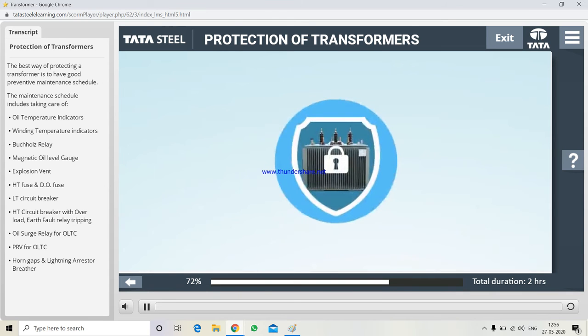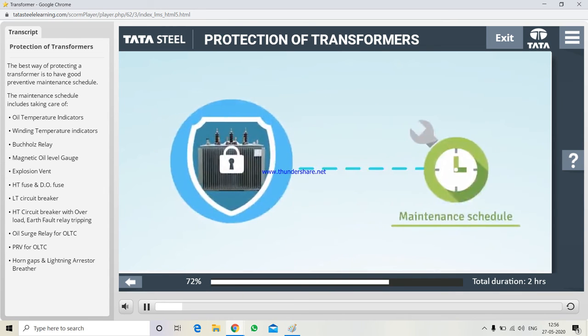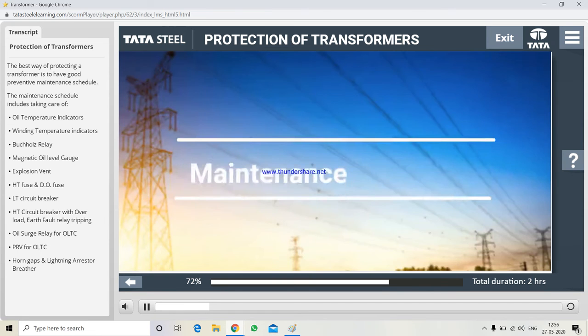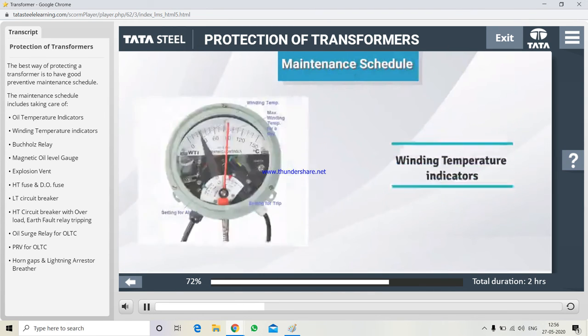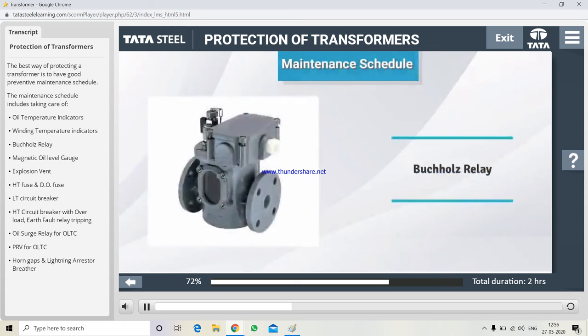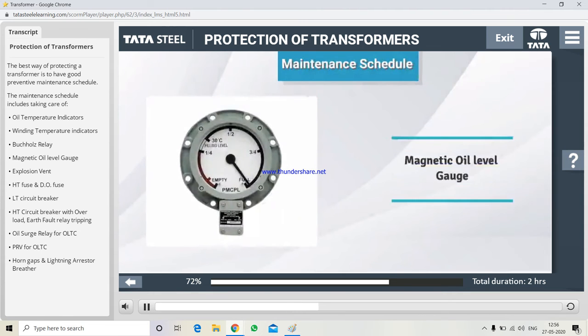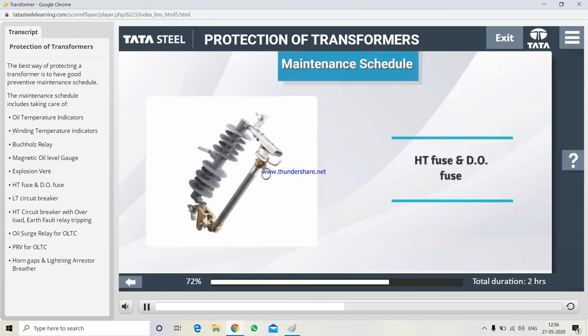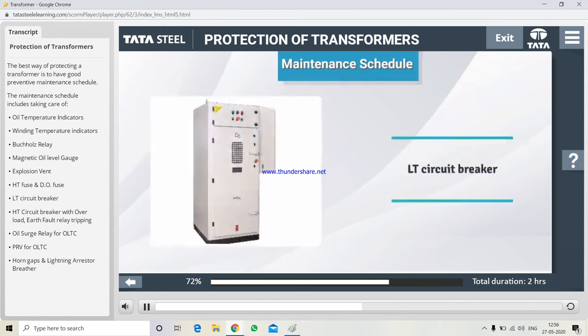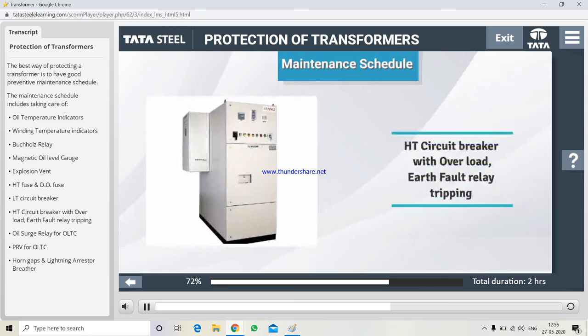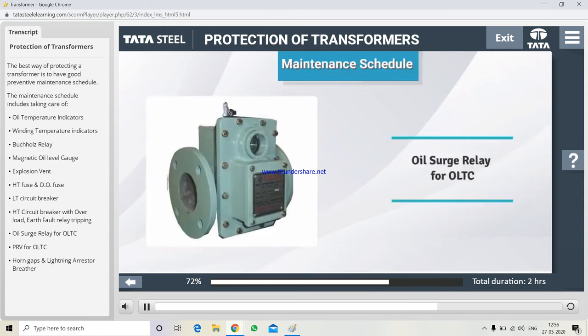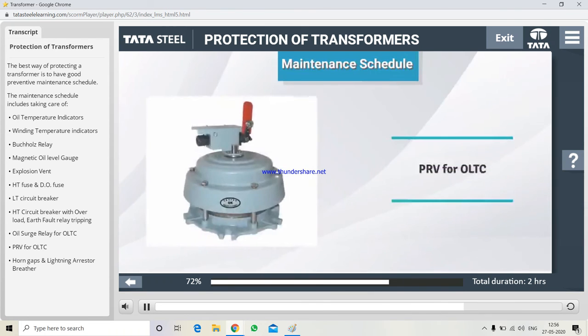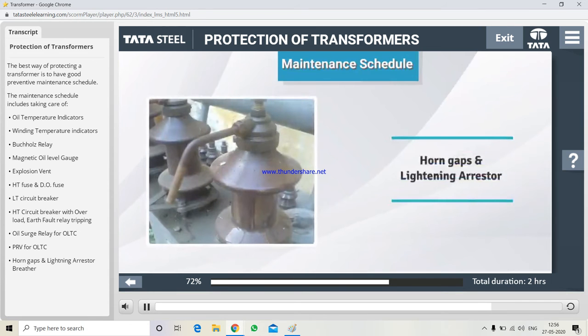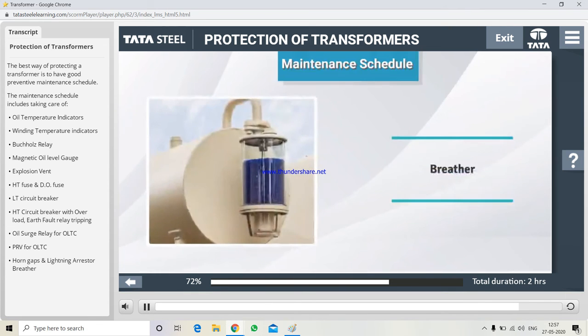The best way of protecting a transformer is to have a good preventive maintenance schedule. The maintenance schedule includes taking care of oil temperature indicators, winding temperature indicators, Buchholz relay, magnetic oil level gauge, explosion vent, HT fuse and DO fuse, LT circuit breaker, HT circuit breaker with overload, earth fault relay tripping, oil surge relay for OLTC, PRV for OLTC, horn gaps and lightning arrestor, breather.